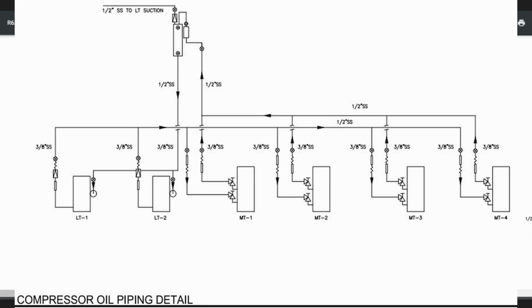So when you run your liquid line, like over to our medium temp, the oil is on the bottom of the liquid line, and it falls into the first liquid line going to the evaporator, and that particular evaporator will get most of the oil. When it goes through the expansion valve, the oil will be on the bottom. And so it tends to lay on the bottom, and the ammonia lays on top in the evaporator. And so when you open that valve, it'll just drain the oil out.